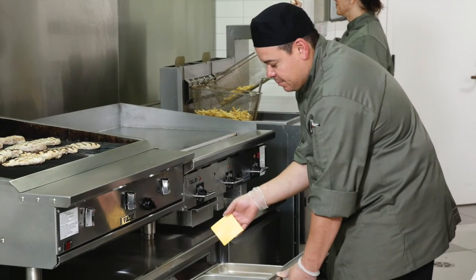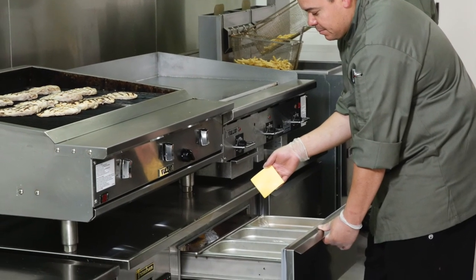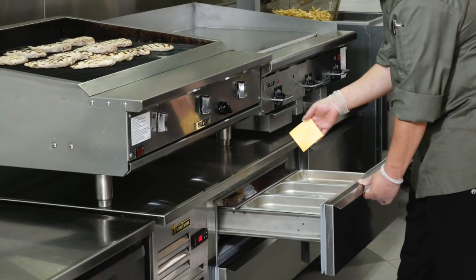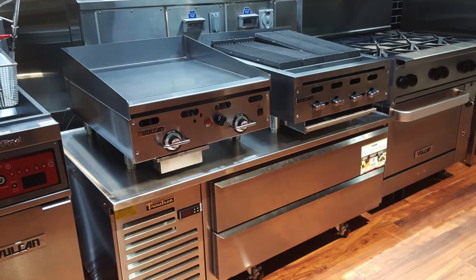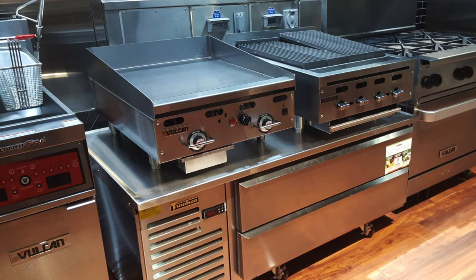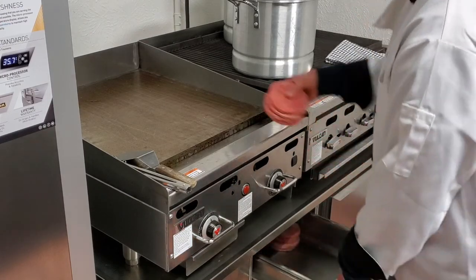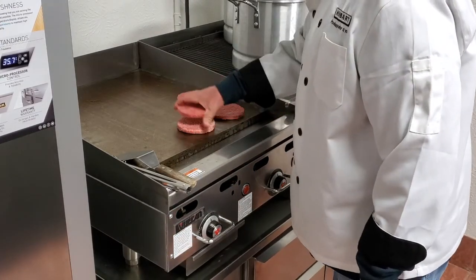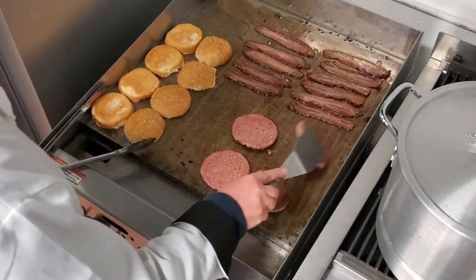As it turns out, some equipment categories pose more of a challenge with this than others because of their specific application — in particular, refrigerated equipment stands. With cooking equipment such as grills, griddles, char broilers, and even fryers always placed on top, the problem posed by excessive grease buildup in the condenser coil can quickly become acute, leading to increased energy usage, decreased performance, and perhaps even an expensive compressor failure.